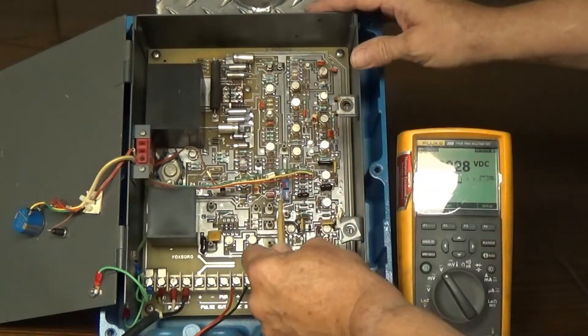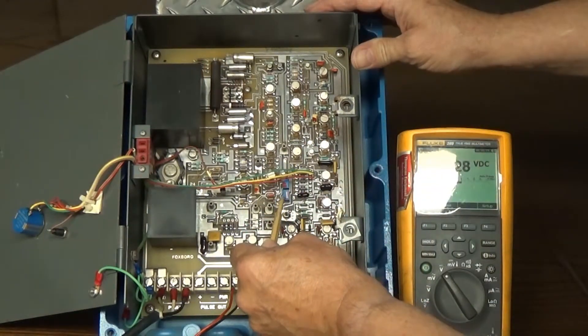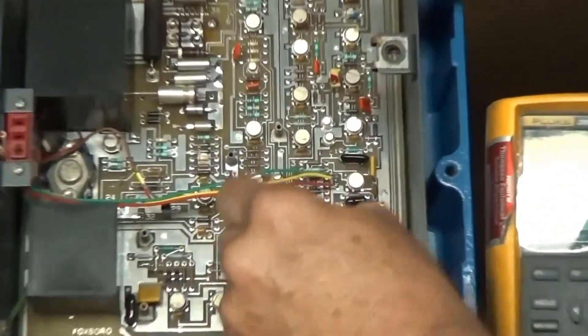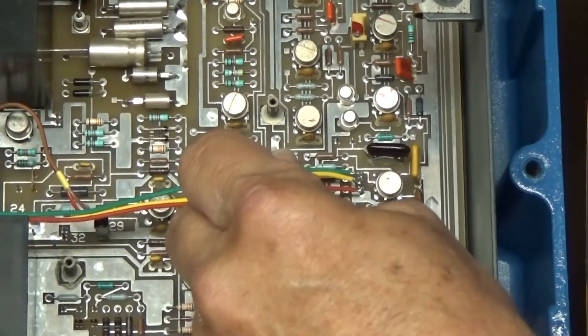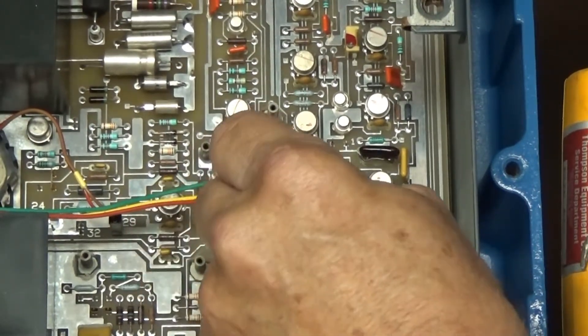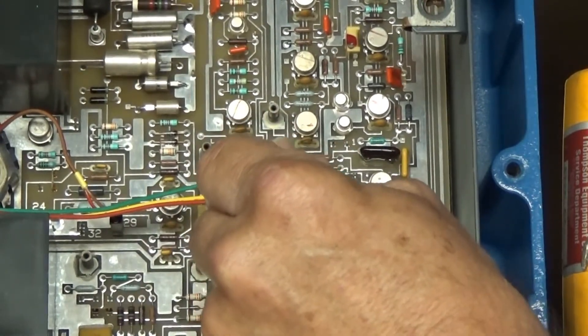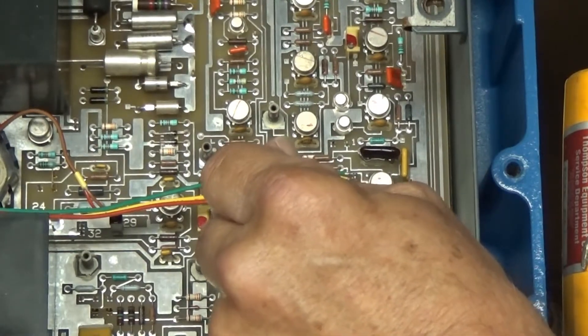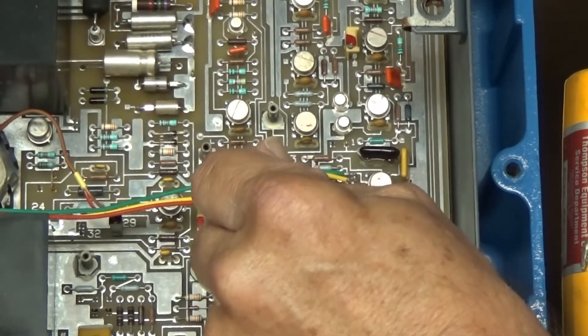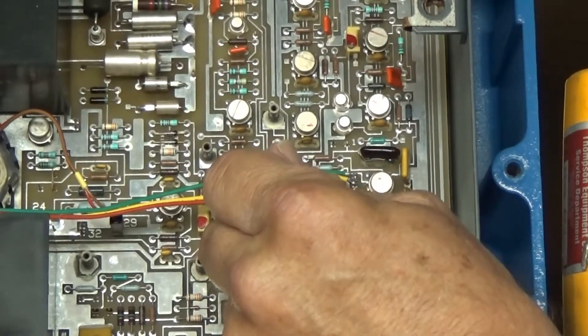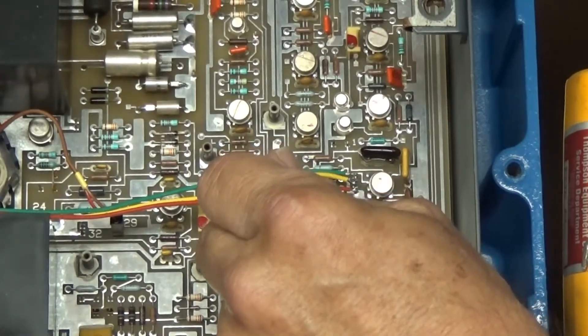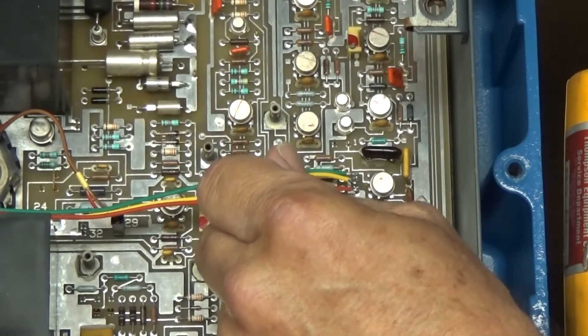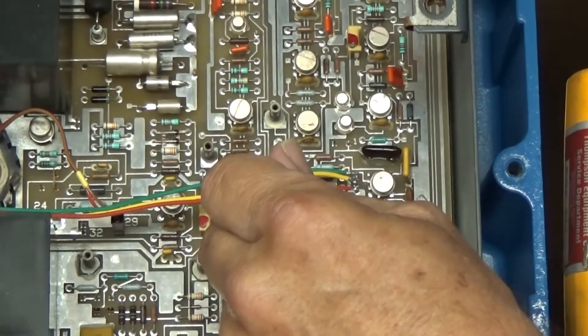And there is a zero potentiometer. It should be clearly labeled as such. And using a tweaker, we adjust this to bring that 1.002 down to 1.0000 if we can get there. Sometimes it's a little touchy. You want to make sure that you don't have any process running, any flow in the tube at all to get this as accurate as possible.